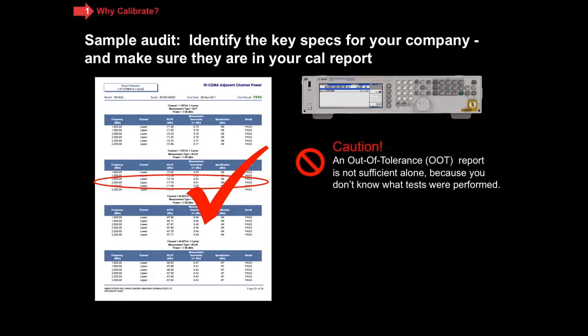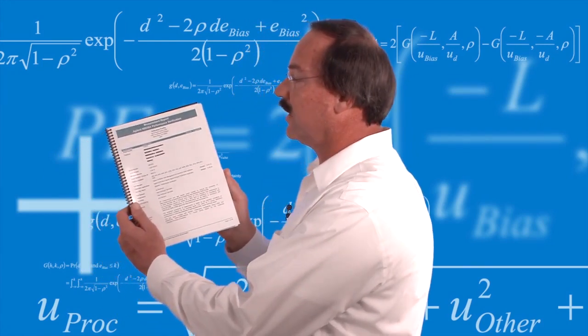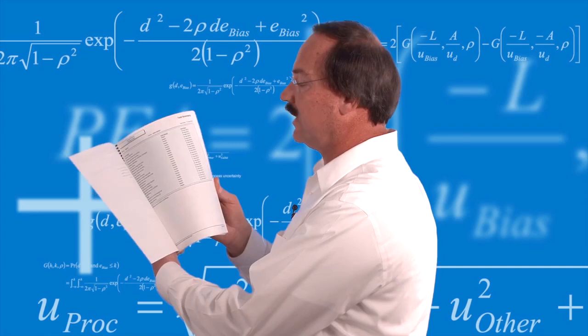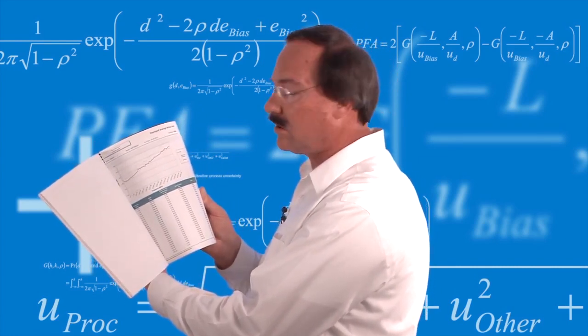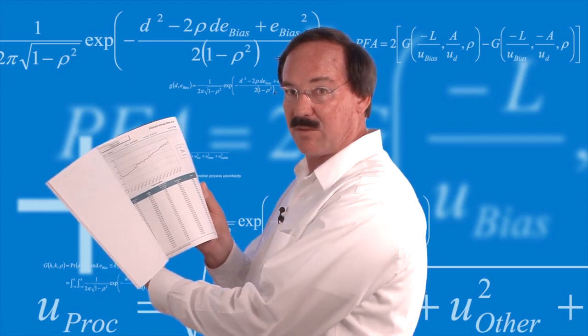If you didn't receive a measurement report, frankly, that's a red flag. If you happen to send your instrument to Agilent, we will give you a measurement report for every measured result — either before adjustments, and if we do adjustments, you will get a before and after adjustments report. Every measurement that we make, you will get a record of. If you're sending your instruments to Agilent, we post online all of your measurement results, and they're available 24/7 for up to seven years. I have a printed-out version of one of those with me right now — this is for a PXI spectrum analyzer, just as an example. What you receive is a full trace report and a summary of tests, and in addition to your calibration certificate, you'll get a measurement result of all the tests that we ran. And if we found it necessary to run adjustments, you'll also receive a second report of all the measurements that we performed after the adjustments were finished.